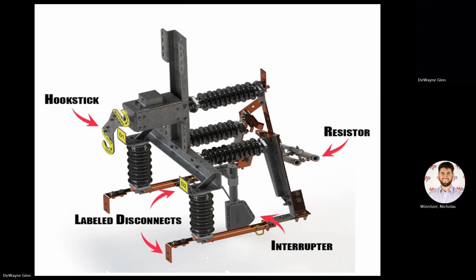So how does that work? I use a hook stick, either bypassed or cut in. Bypass meaning I'm bypassing the voltage regulator. And all I do is pull down on it. If you look to the far right, try to visualize that you see those reverse loop contact jaws. It's a blade that goes right there. It's coming down. It would slap across and it picks up on a copper trolley and transfers all that high energy that's in the voltage regulator through that loop to these high voltage resistors and dissipates that energy and controls it.